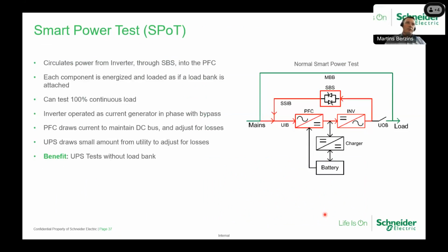As mentioned earlier, we have a smart power test or SPoT mode, which we are integrating in our UPS models. So a very smart way to test the UPS. So basically, what does it mean? Once the UPS is installed and the Schneider Electric field service engineer arrives at your site for a startup, they can simulate this smart power test, which is actually a test to ensure that your UPS can work at 100% continuous load. So before connecting the UPS to the actual load, we can simulate the situation when the 100% load is connected without bringing in any external load bank. So basically what the UPS does, it circulates power internally through the rectifier and inverter, and in this way it simulates this load test.